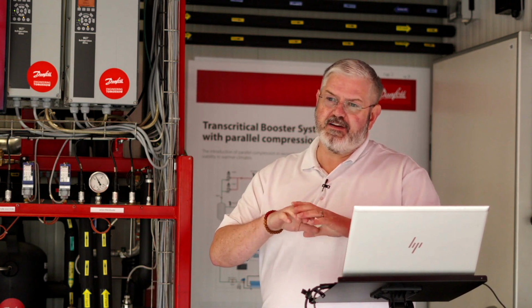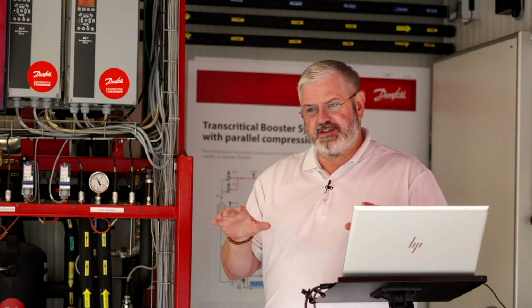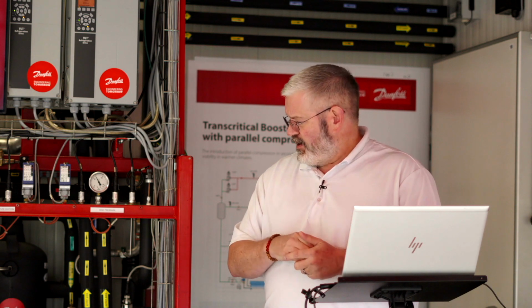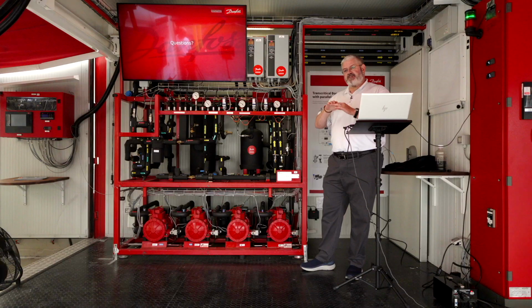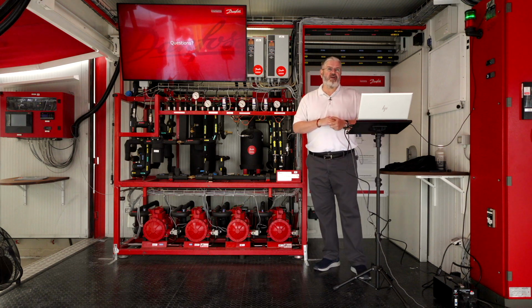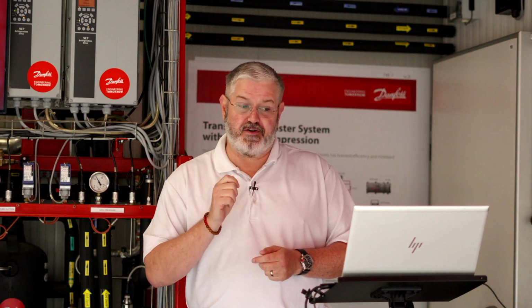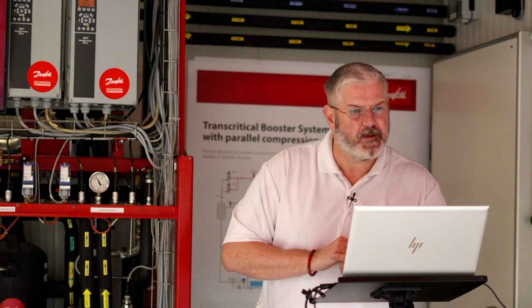Once you've got the entire system down to temp on all your low temp load and all your medium temp load, you continue charging the flash tank until you're above the bottom sight glass, and then the system is charged. So I hope that answers the question, but it's really important that you don't put liquid CO₂ in a system that's below 100 pounds of pressure.